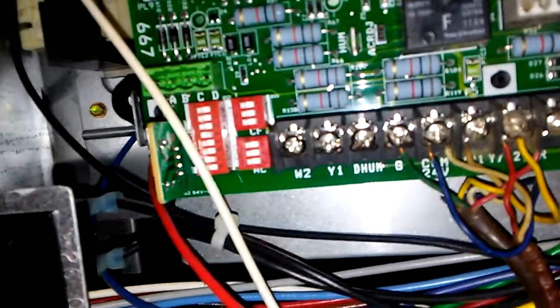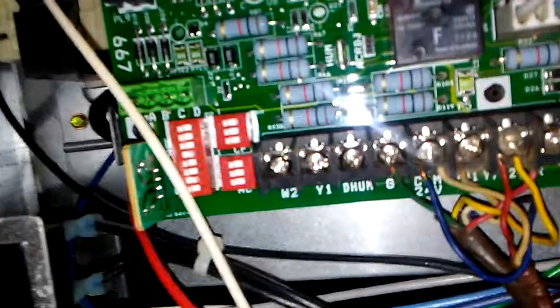You see Y1, that's where that yellow wire was. I moved it to Y2, which means high speed or second stage. The outside unit is only one stage, so I had to move the red wire with it too. As you can see, where the red and yellow wire is, that's Y2. It's hard to tell, can't focus.